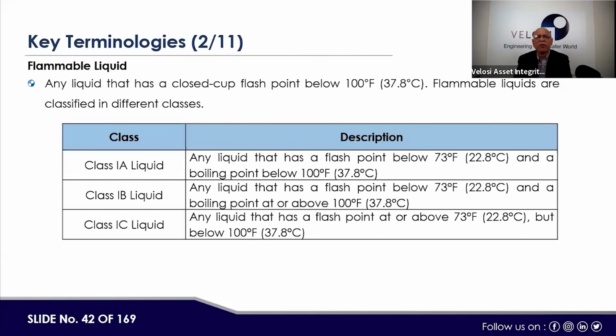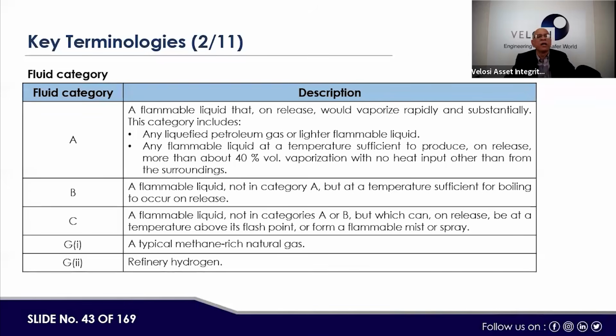So what is a flammable liquid? Anything which can catch flame is called a flammable liquid. It has various classes, Class 1A, 1B, and 1C, and it is related to the flash point. If the flash point is below 22.8 degrees Celsius, this is Class 1A. If the flash point is below 22.8 degrees Celsius and the boiling point is at or above 37.8 degrees Celsius, it is Class 1B liquid, and any liquid that has a flash point above 22.8 degrees but below 37.8 degrees is called Class 1C liquid. And when you identify these liquids, they are selected for the area classification and for the selection of the relevant electrical and instrumentation apparatus, if that would be installed in that area. Similarly, these categories are further categorized as fluid category A, B, C.